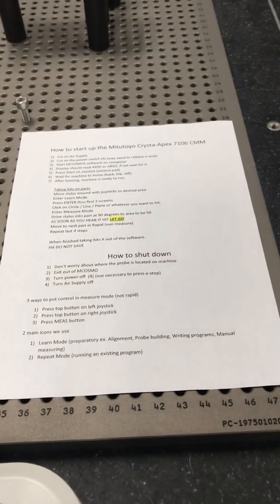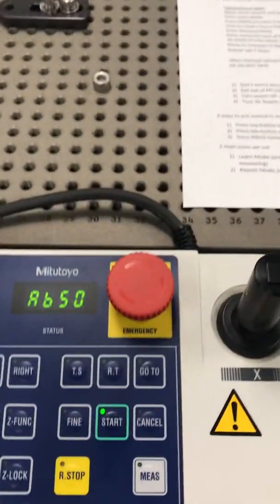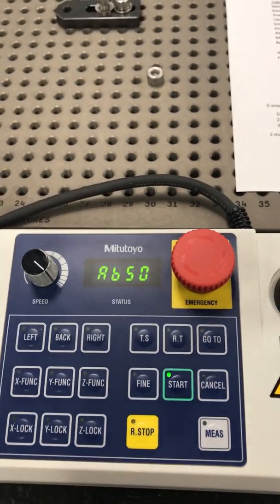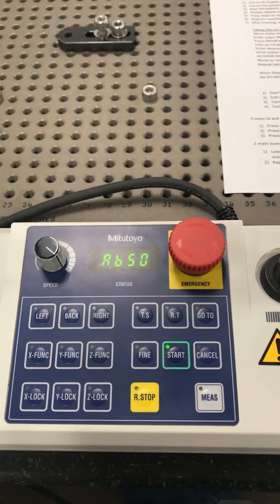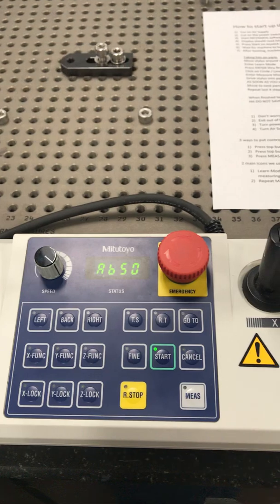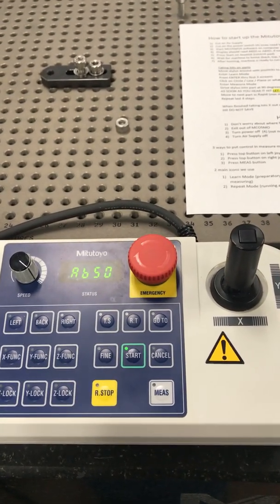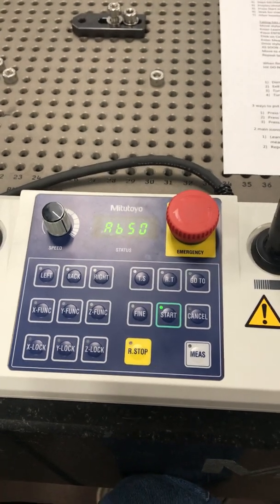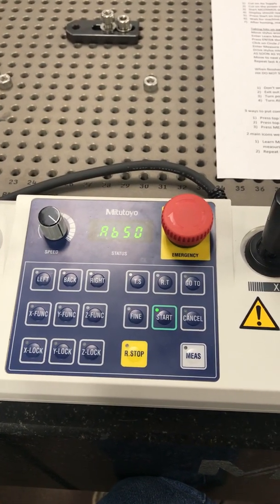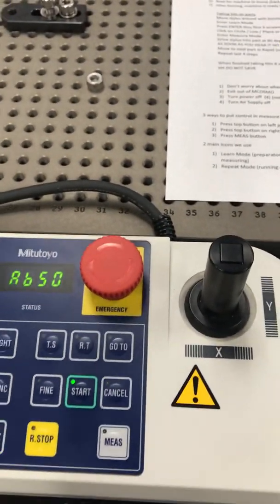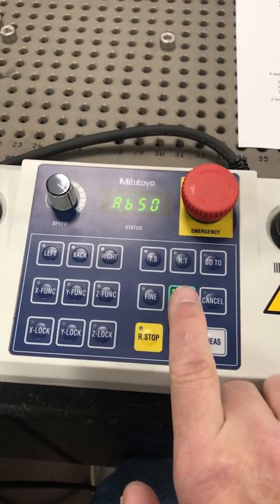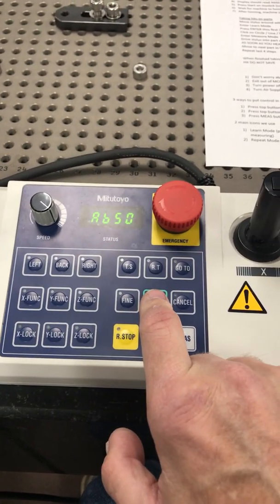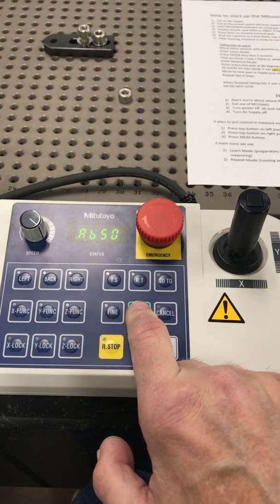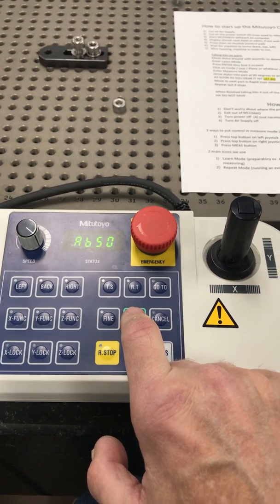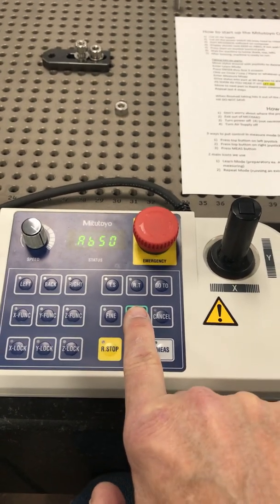All right. Number four, the display should read ABSO or it looks like A650, but it's actually ABSO, which means absolute. So don't do anything after you start the MCosmos software until you see ABSO, A650, whatever you want to call it. Number five, press start on the joystick. That is this button. This will initialize the homing procedure of the CMM, very similar to on the CNC mills where it says startup. This is your startup on the CMM.